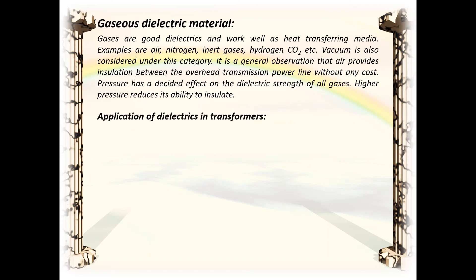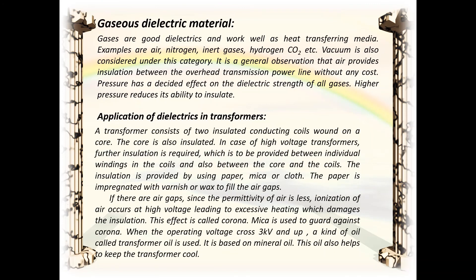A transformer consists of two insulated conducting coils wound on a core, which is also insulated. In high voltage transformers, further insulation is required between individual windings in the coils and between the core and coils. Insulation is provided using paper, mica, or cloth, with the paper impregnated with varnish or wax to fill air gaps. Air gaps can lead to ionization at high voltage causing excessive heating — this effect is called corona. Mica is used to guard against corona when the operating voltage exceeds 3 kV, and transformer oil (based on mineral oil) is also used, which helps keep the transformer cool.